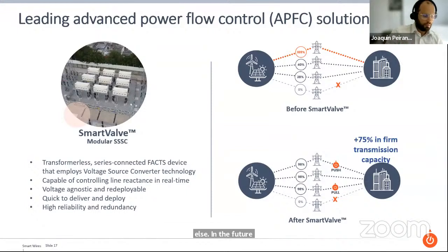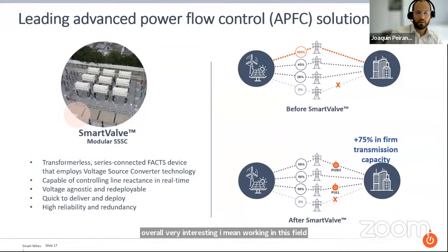So that's overall very interesting. Working in this field for the past 10 years, you see a lot of situations. To give you an example, in Chile or Brazil, you have the backbone grid, the 500 kV or high voltage lines that you build, but the transmission lines running in parallel, the older ones, 138 kV, 115, 230 kV, are the limiting elements. They act as bottlenecks for us to transfer the flow through the high voltage lines. This type of solution can solve those imbalances in a relatively quick fashion.